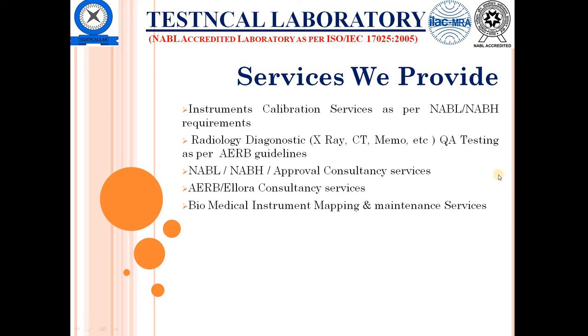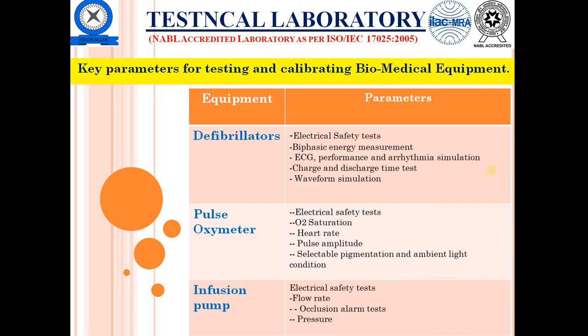Maintenance activity, preventive maintenance and seasonal or timely maintenance, we say. Key parameters for testing and calibration of biomedical instruments. Mostly, a few of the biomedical instruments we have taken on this slide, like defibrillators.